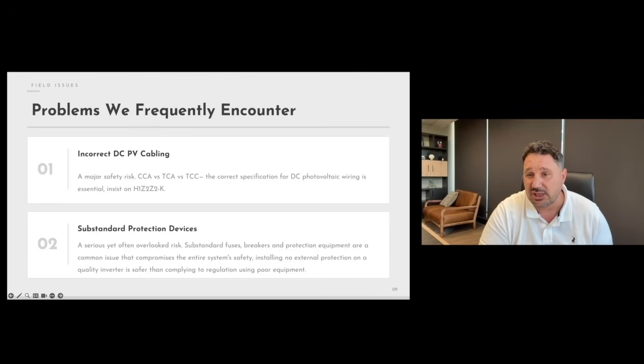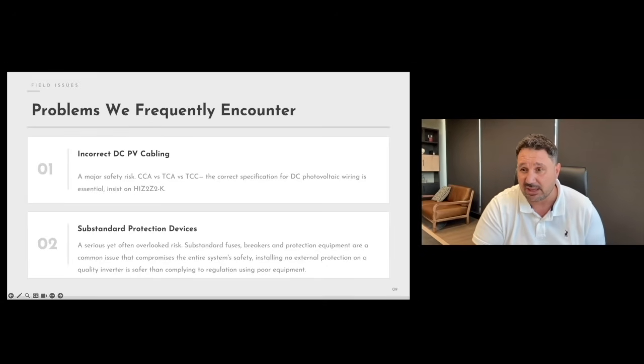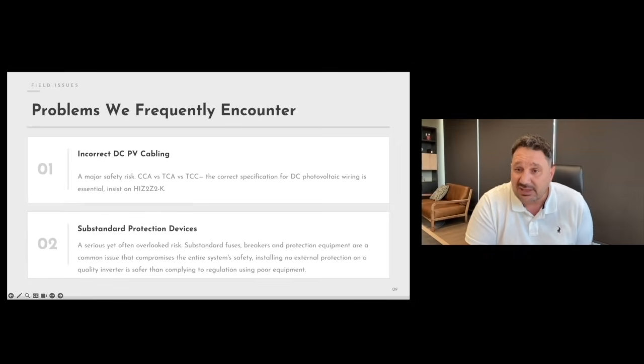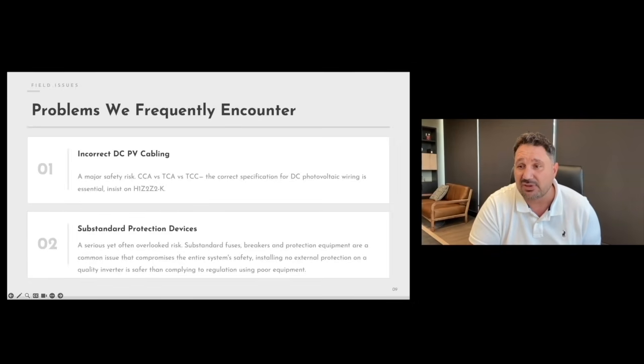A proven solution lies in the use of TUV-certified or H1Z2Z2-K cables. These cables are specifically designed in accordance with international standards for PV applications, featuring double insulation, excellent UV and weather resistance, and high tolerance to temperature, flames and fire. As a result, they offer reliable long-term performance and reduce the likelihood of electrical faults.